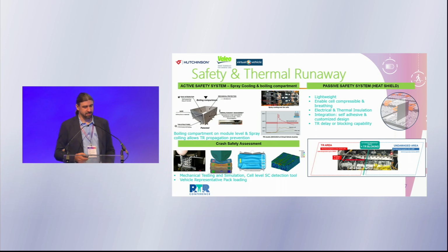We have an active safety system with boiling compartments that can be put around modules, to contain a thermal runaway in a module. We also have a passive safety system from Hutchinson, with lightweight sheets that can be placed between single cells, cell stacks, or modules, to really block or delay thermal runaway propagation, assuming that a thermal runaway event on one cell cannot be completely avoided at 100%.